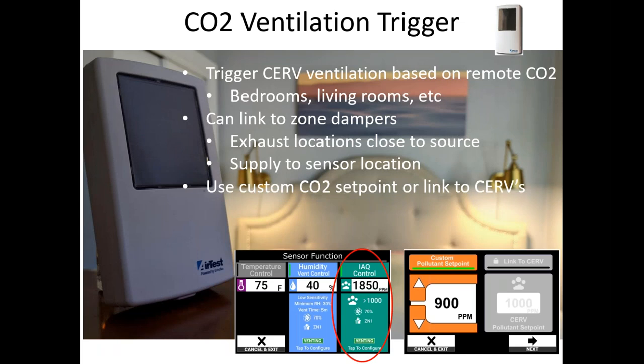The remote CO2 sensor also has temperature and humidity built into it. So you can activate all those functions at once if you want. But you can now use the CO2 level in a specific space to trigger ventilation on the CERV. Generally this would be in bedrooms or living spaces where you want occupancy in that room to trigger ventilation sooner than the CERV may pick up from the overall house air quality.